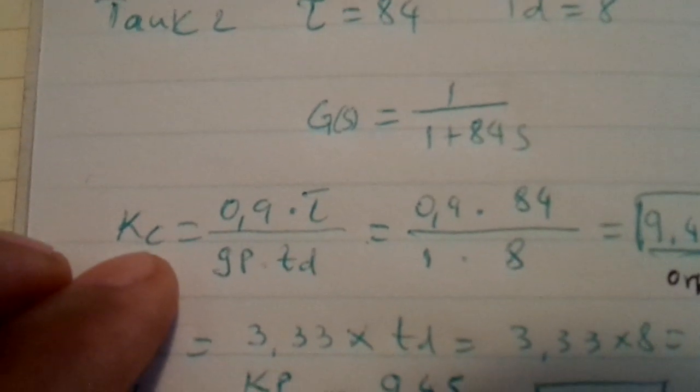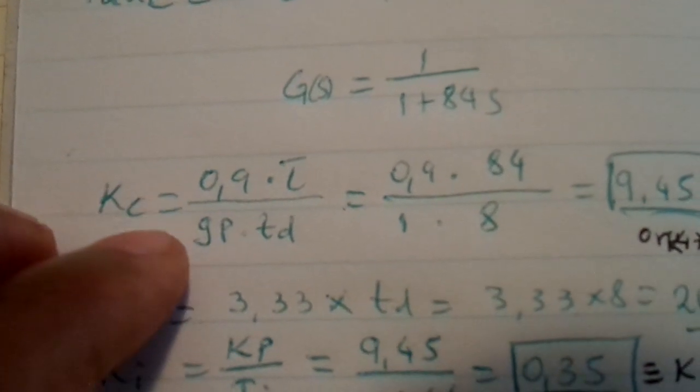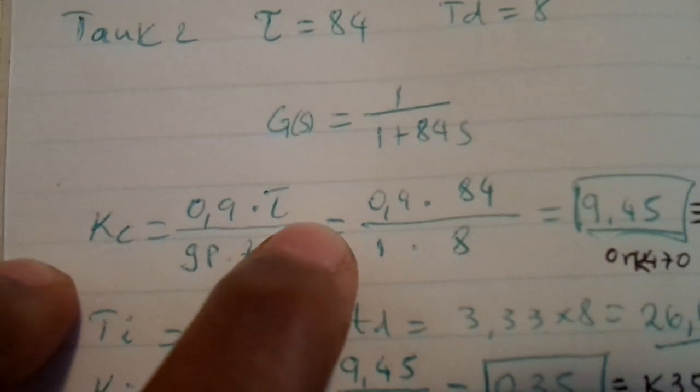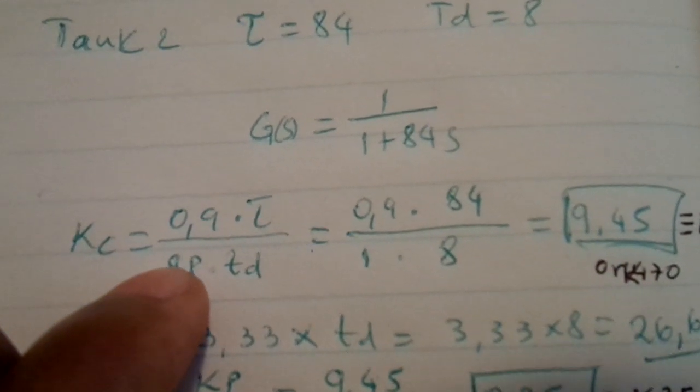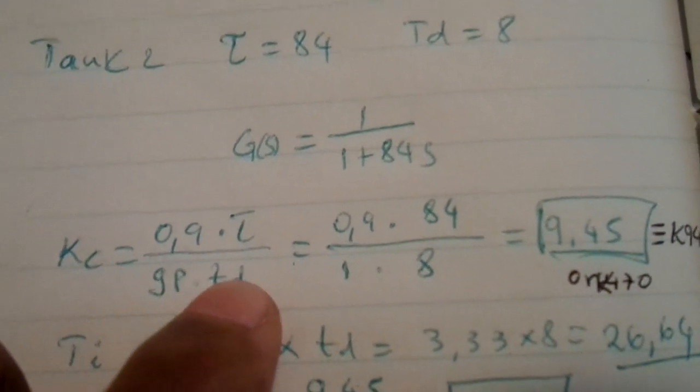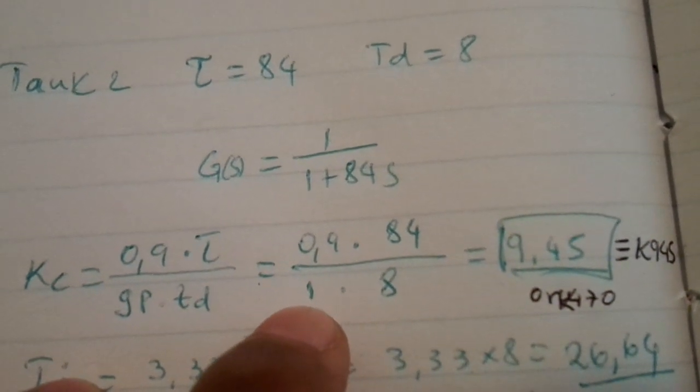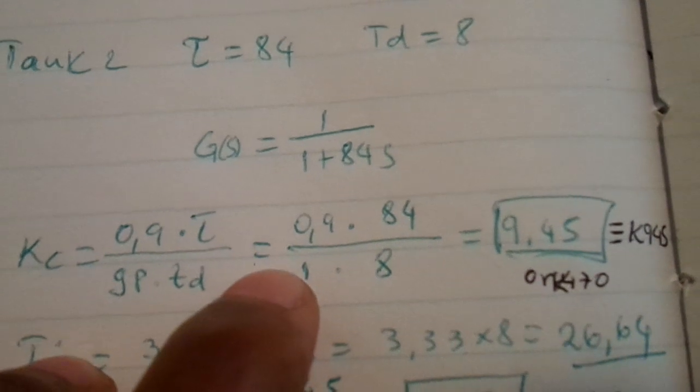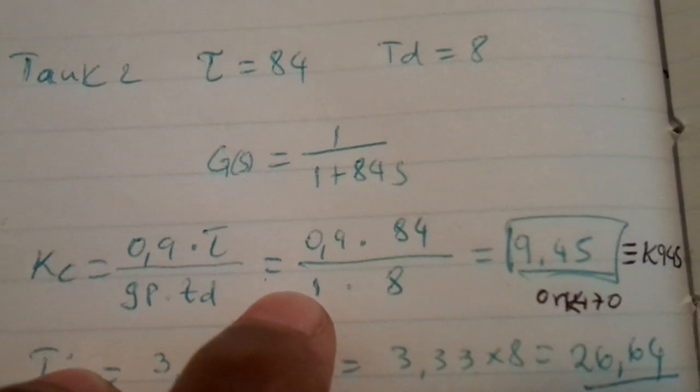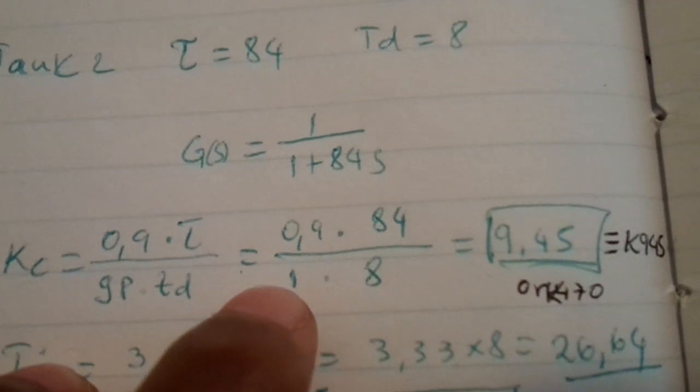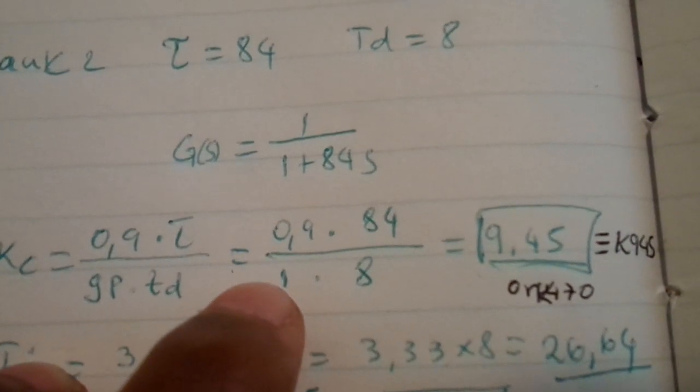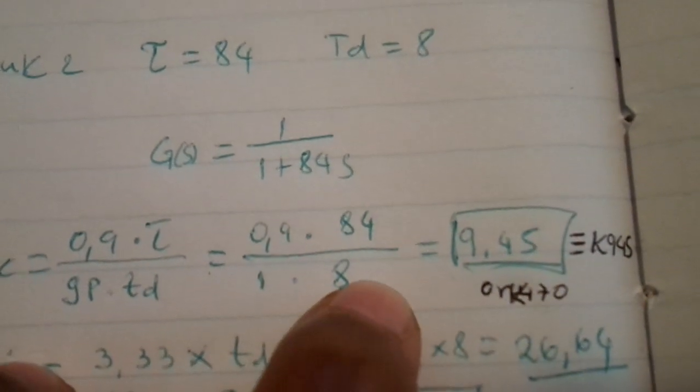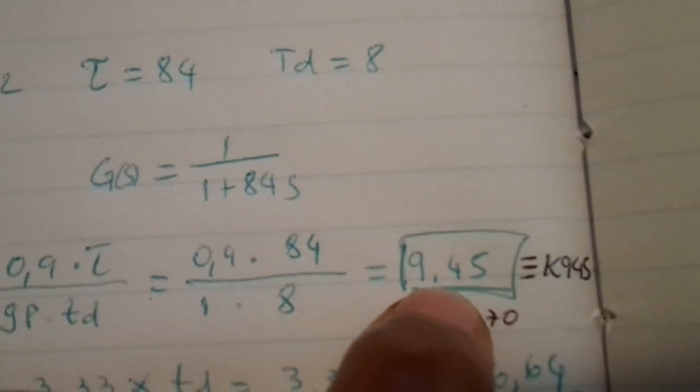So now using Ziegler-Nichols for open loop, the controller gain will be 0.9 times the time constant over my plant gain times the time delay. My plant gain is one. I didn't specifically mention those calculations on that Word document, but it's one. I can provide you with this document if you're interested. So 0.9 times 84 over 1 times 8, which is the time delay, and I got 9.45.